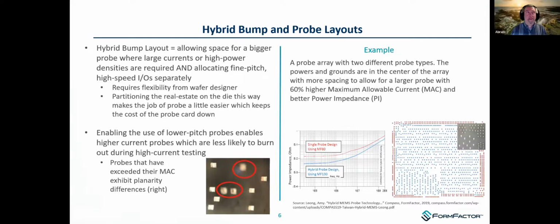How many bumps have you seen in terms of a limit? We've seen cards that go deep into the tens of thousands, 20 to 40,000 probes. And on full wafer contact, we might be talking on the order of maybe 180,000 probes. But those are different technologies. On a vertical array that has to move around with more fidelity but lower parallelism, you might see about 10 to 40,000 probes on the ambitious designs and the high density hybrid probe layouts.